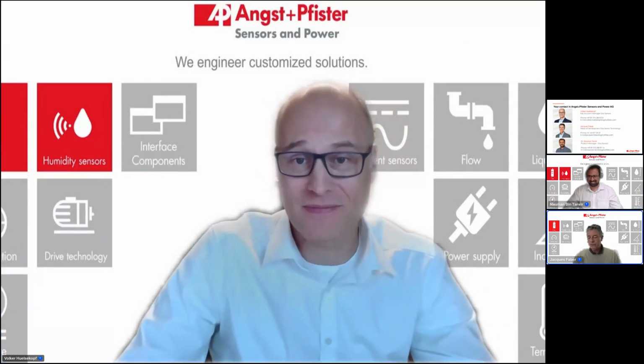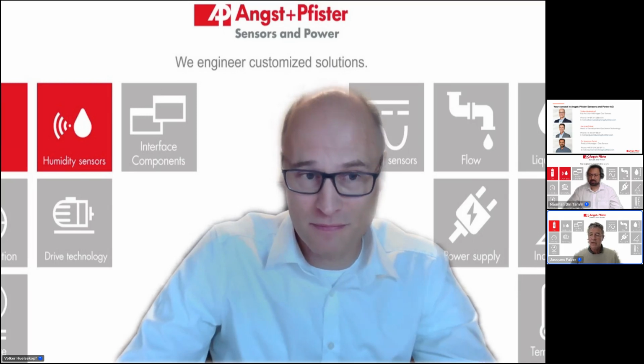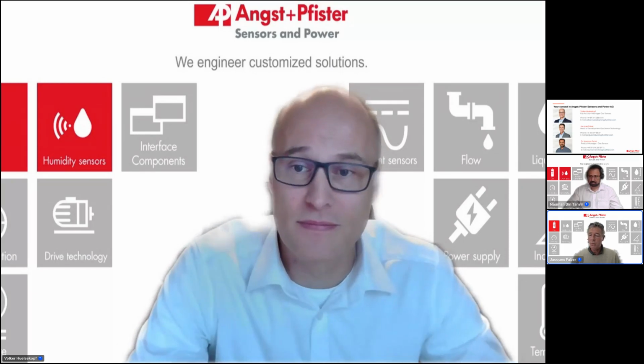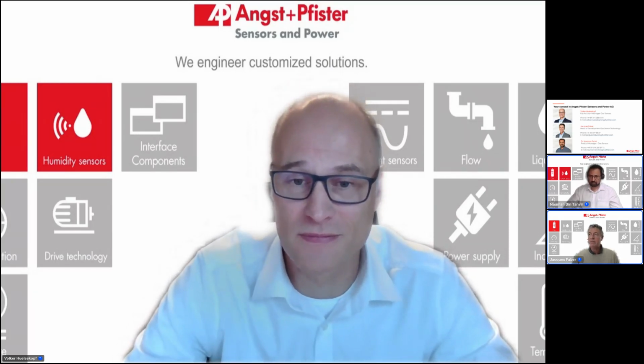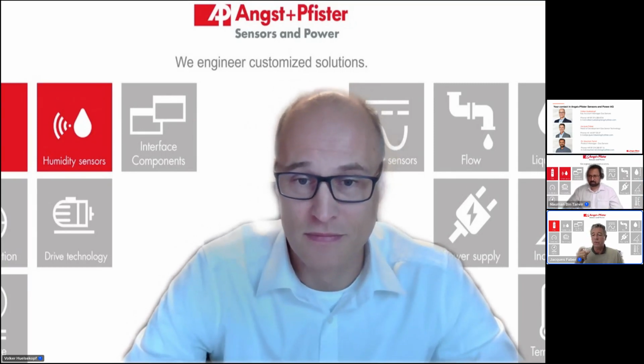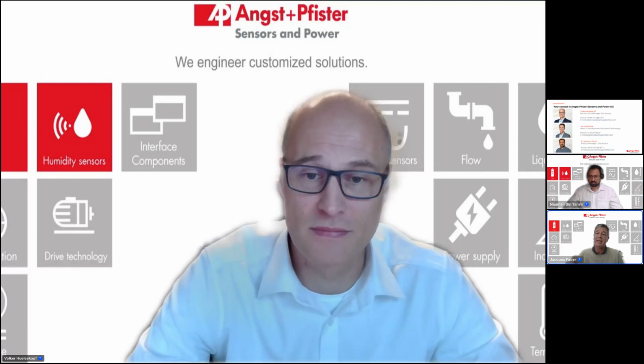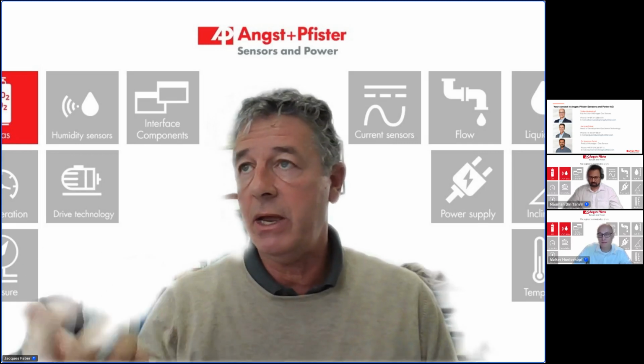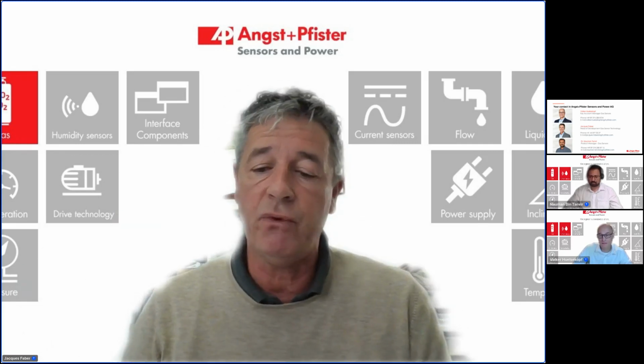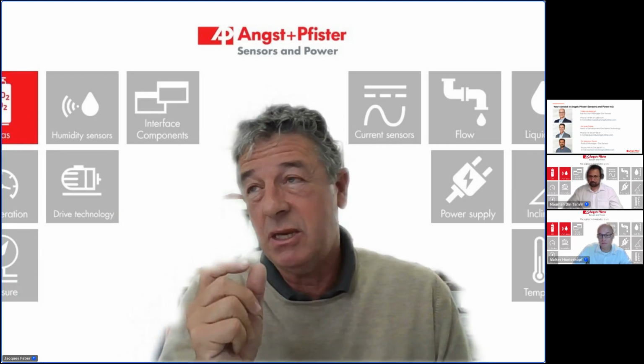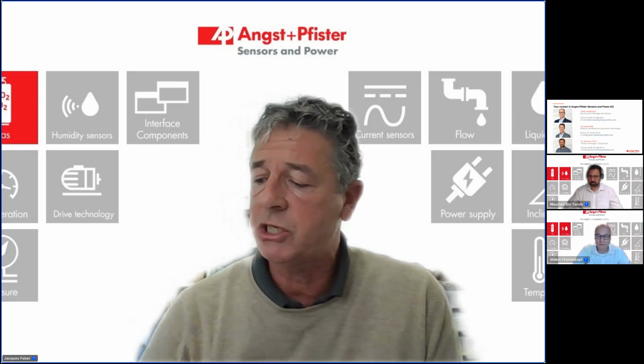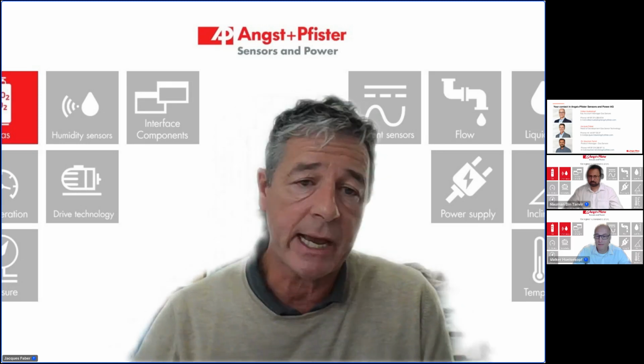Actually, regarding cross sensitivities, the paramagnetic system is very, very good. There is a table available in the manual where you see all the different gases, and if you have some gases where you know that the amount of cross sensitivity gas is quite high, you can do some calculation and delete the influence. But this parameter for calculating is normally very low with all gases. There's actually just one which is quite high, that's the nitrogen dioxide.